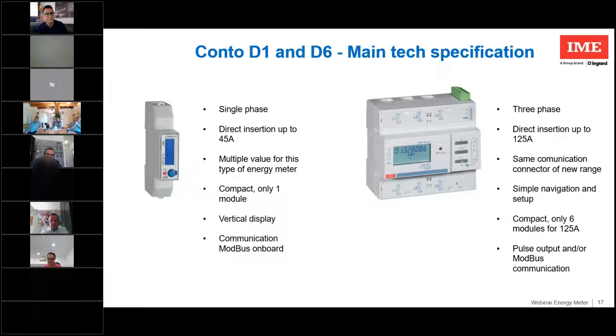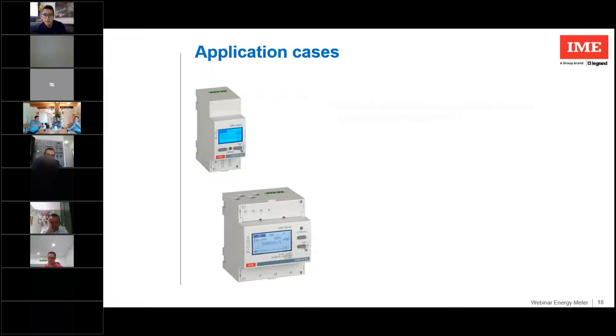In summary, the energy meters are the basis of measurement. As a result, there are various fields in which to use them, from industrial to residential, up to counting the energy in charging columns for electrical cars, or at the top of the box in data centers. So there are a lot of application cases for this energy meter. There isn't a standard one you can use, because as I said, the energy meter is the basis of measurement, along with, for example, the current transformer or the voltage transformer.